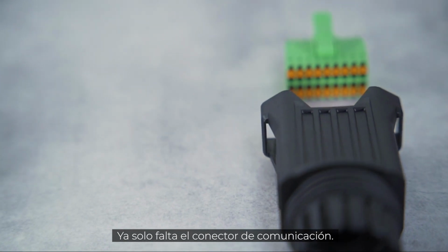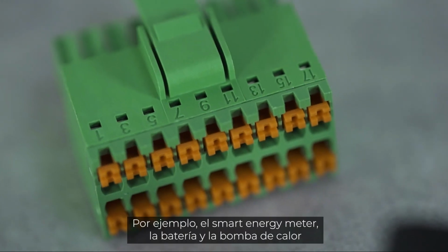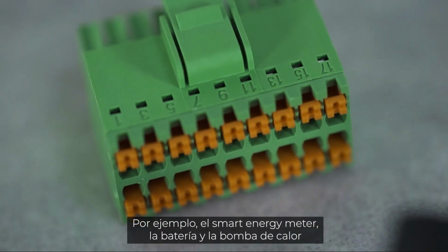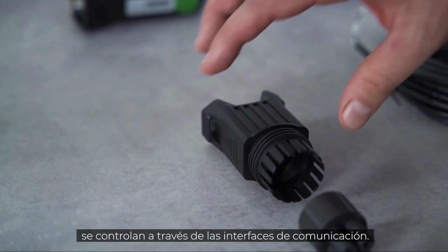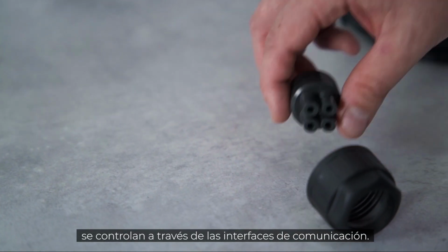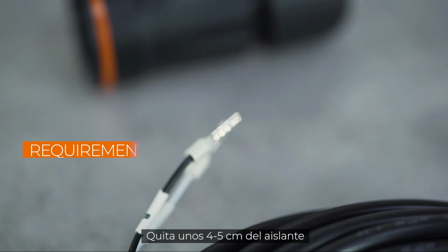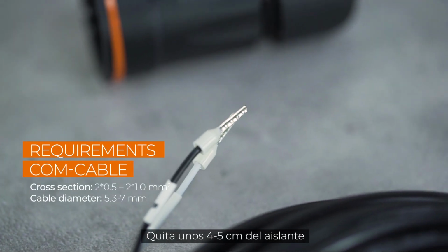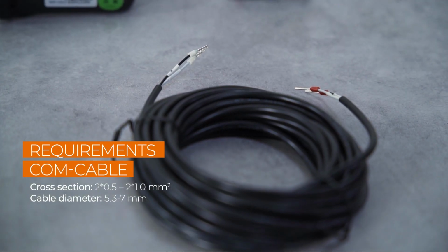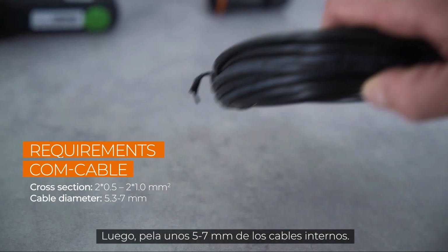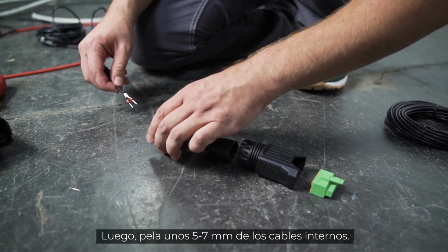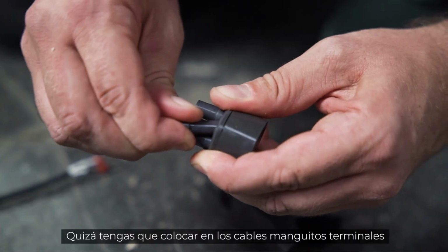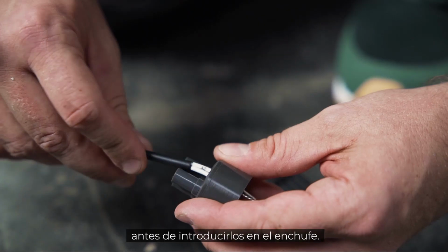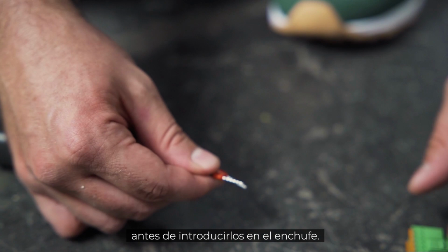Now only the communication plug is missing. The smart meter, the battery and the heat pump, for example, are controlled via the communication interfaces. Remove approximately 4 to 5 centimeters of the cable sheath of the communication cables. Then strip approximately 5 to 7 millimeters of the inner cables. If necessary, you may have to fit the cables with end sleeves before you push them into the plug.